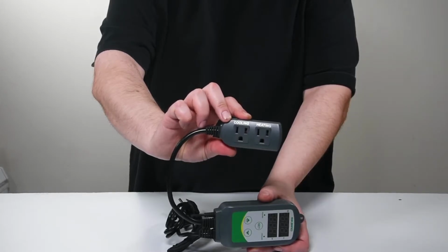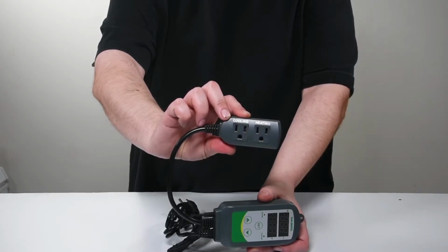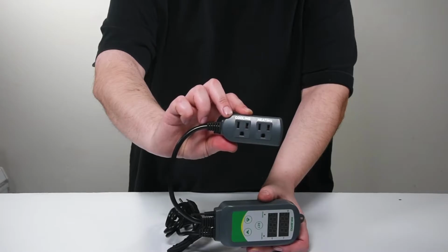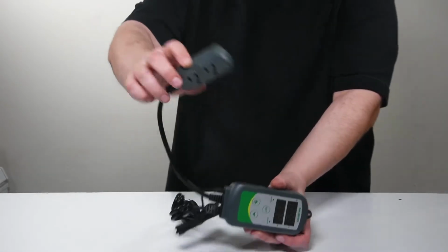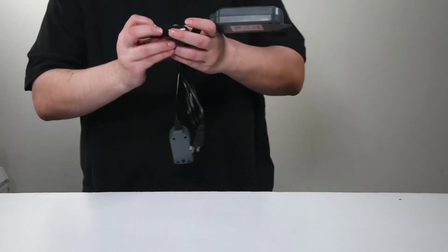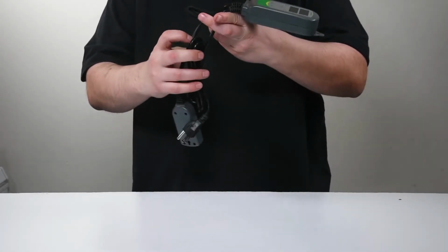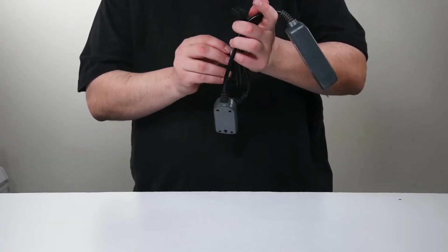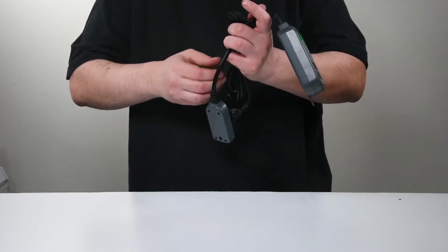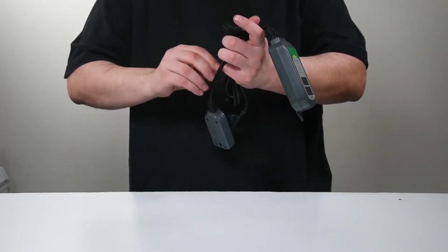That's a great place to start talking about how to set this up. First, make sure that the heating and cooling appliances have power cables that will reach the appropriate power socket. This is important because if you plug your heater into the cooler socket, you will heat instead of cooling, thus doing the exact opposite of what the temperature controller intends to do.